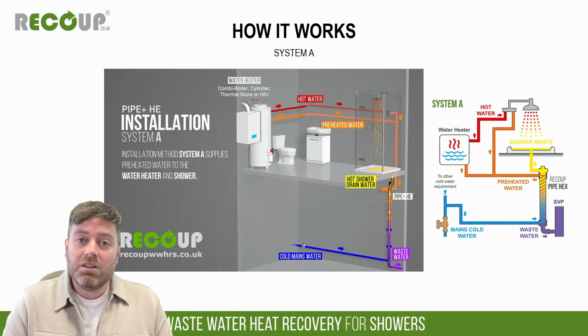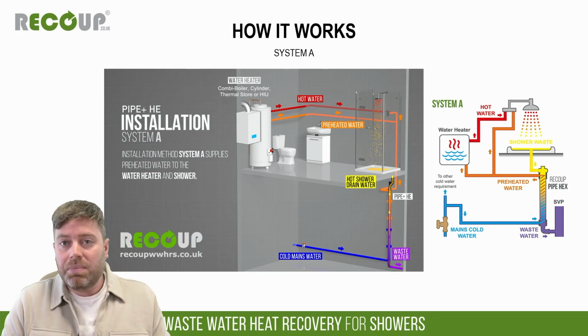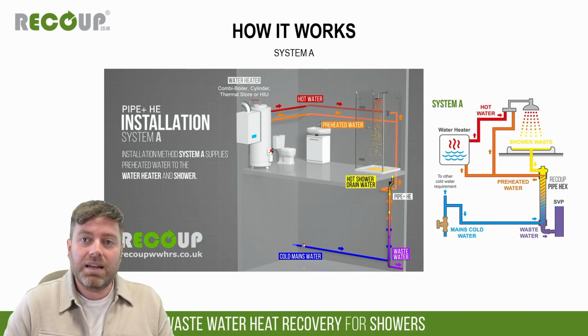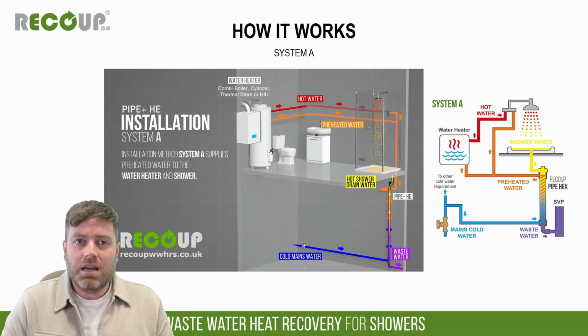So as I said, there's 3 recognised ways to use that preheated water. They're known as System A, System B, and System C. All they do is denote what you do with that preheated water. So there's 3 different ways you can use it. So once the preheated water leaves the wastewater heat recovery system, you can either install a System A, System B, or System C. So System A is the most efficient installation method. So you can see on the schematic here with System A, we take that preheated water and we send it to 2 places. So the preheated water leaves the unit and it goes to the cold side of the shower's thermostatic mixer valve, and it goes to your hot water source. So that hot water source could be, as I said, a combi boiler, a hot water cylinder, an HIU, doesn't really matter. So that's your System A installation method.